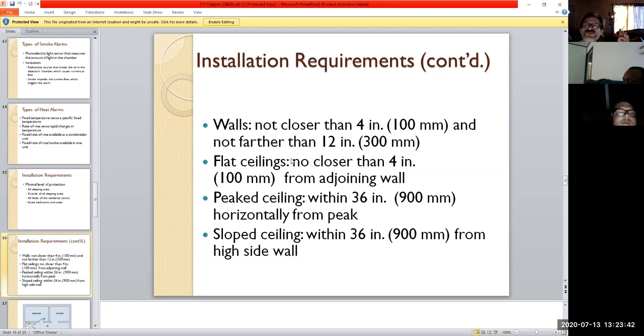They also have requirements for where it can be installed. You can't put it in certain areas where smoke or heat wouldn't reach—basically common sense, and the code just specifies don't put it here or here. As for how far from the ceiling: on a wall, no further than 12 inches and no closer than 4 inches to the ceiling. Same with a flat ceiling—no closer than 4 inches from the adjoining wall, because a corner can become dead space where smoke just flows around it. You want to get it out of the corner into the general area. Same with vaulted ceilings—peak ceilings need the alarm within 36 inches of the peak, same with sloped ceilings.